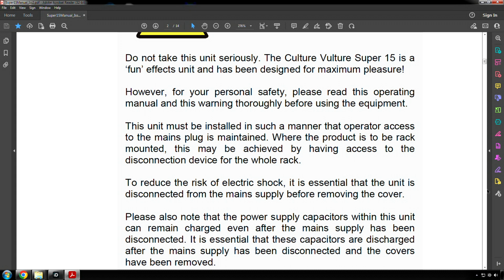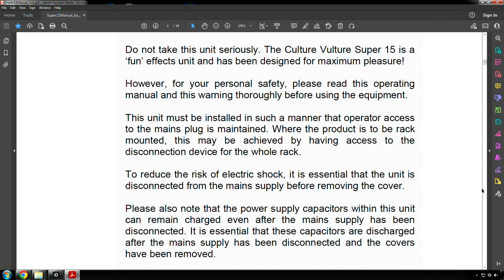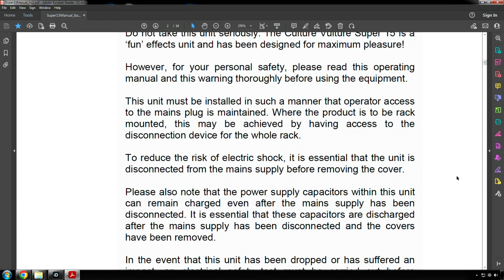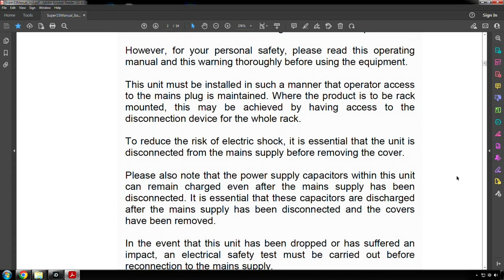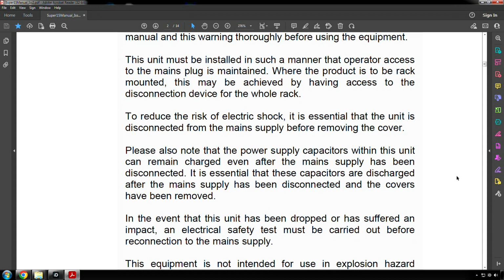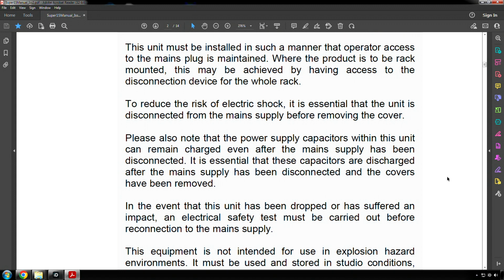This unit must be installed in such a manner that operator access to the mains plug is maintained. Where the product is to be rack mounted, this may be achieved by having access to the disconnection device for the whole rack. To reduce the risk of electric shock, it is essential that the unit is disconnected from the mains supply before removing the cover. Please also note that the power supply capacitors within this unit can remain charged even after the mains supply has been disconnected. It is essential that these capacitors are discharged after the mains supply has been disconnected and the covers have been removed.